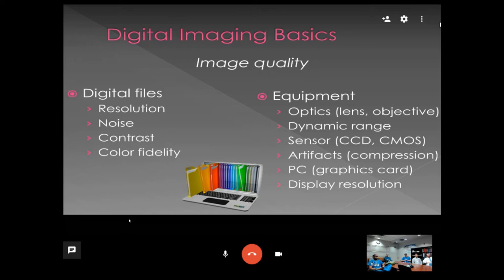Looking at the optics, in pathology you have a microscope, so we're looking at the objective—does it have a high NA, how much light is passing through—looking at the dynamic range of the camera, the sensor type, quality and size, and artifacts, which can come into play with image compression. Because these are all digital images, do we have adequate computing processing and a graphics card to render these images appropriately? What about our actual monitor or display—how high resolution is it? So there are a lot of factors and variables that come into account with image quality.